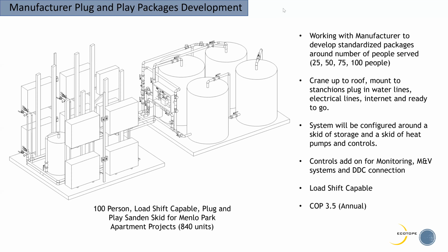This will allow third-party manufacturers or assemblers to put these systems together. So we're aligning with how the central gas products are. A lot of the central heat pump water heating products currently available in the industry are mostly plug and play. Some are built up, but what we're trying to do here is get systems to the point where we can plug and play. So this is really exciting. We've got 840 units that we're looking at putting more or less 100-person skids scattered around the roof. And what this does is it drives you to roughly 60 to 70 unit decentralized loops.